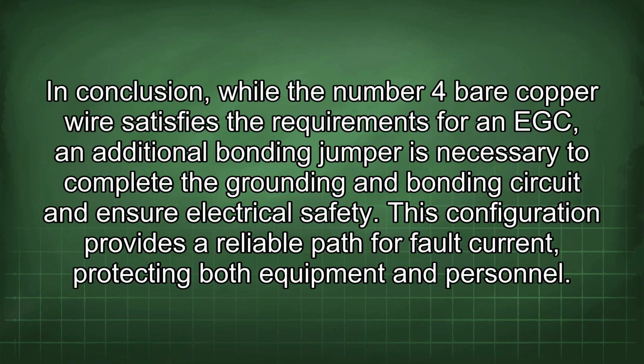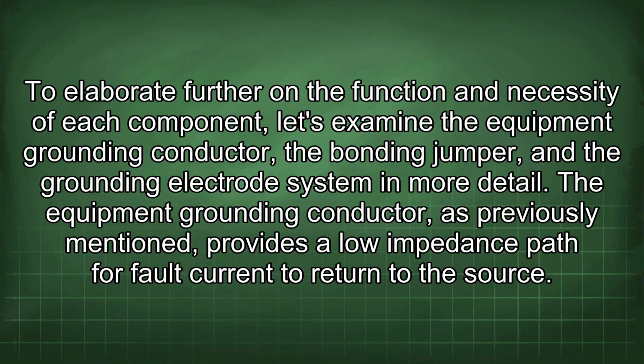In conclusion, while the number 4 bare copper wire satisfies the requirements for an EGC, an additional bonding jumper is necessary to complete the grounding and bonding circuit and ensure electrical safety. This configuration provides a reliable path for fault current, protecting both equipment and personnel. To elaborate further on the function and necessity of each component, let's examine the equipment grounding conductor, the bonding jumper, and the grounding electrode system in more detail.